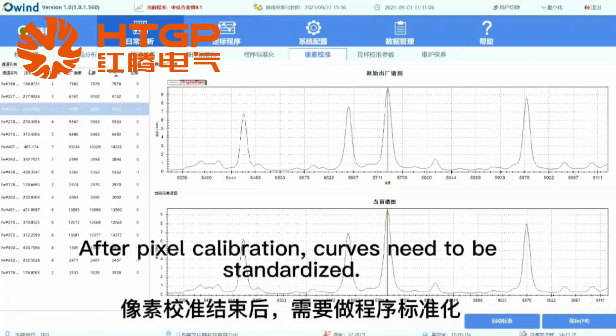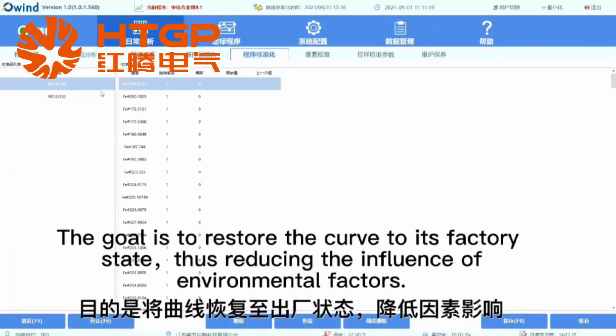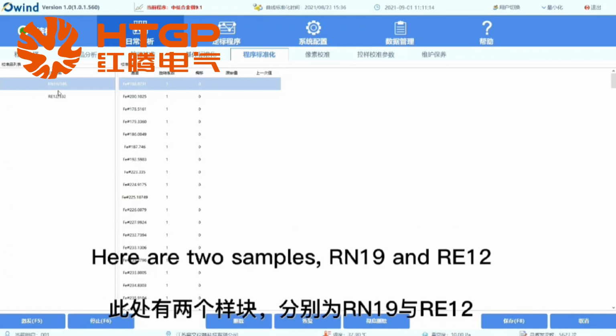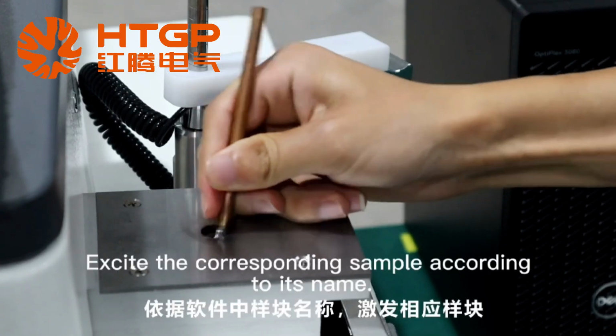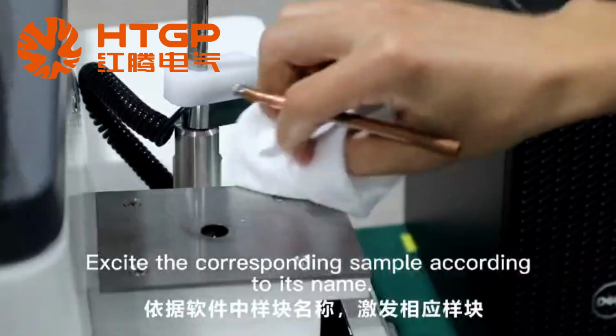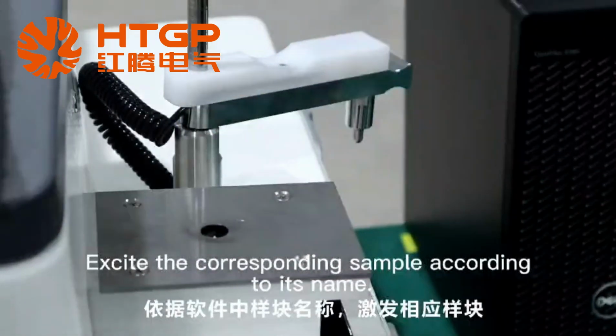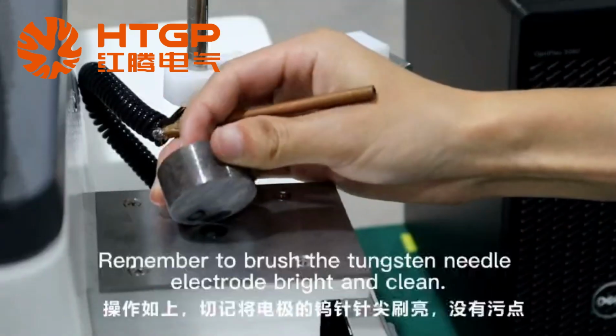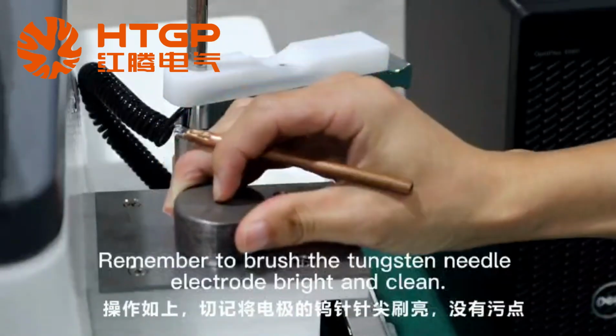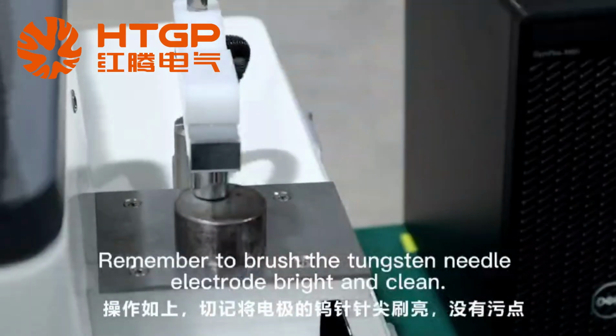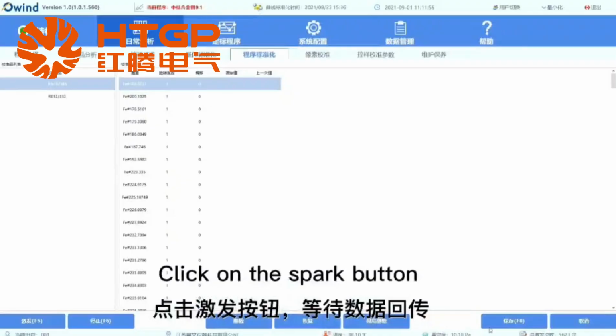After pixel calibration, curves need to be standardized. The goal is to restore the curve to its factory state, thus reducing the influence of environmental factors. Here are 2 samples, RN19 and RE12. Excite the corresponding sample according to its name. Remember to brush the tungsten needle, electrode bright and clean. Click on the spark button.